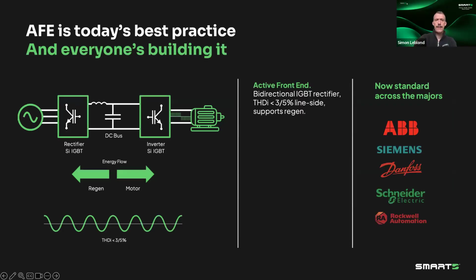If we talk about the active front end, they are getting more and more prevalent in the industry, so we are seeing more and more manufacturers roll them out. You'll have varying degrees of performance. Some will state 3%, 5%, typically at full load, which is not necessarily what you're looking at day-to-day, because if you were running at full load, you wouldn't have a VFD. So it's important to also look at the performance at that 50, 70% mark where you're actually going to be running your VFD.